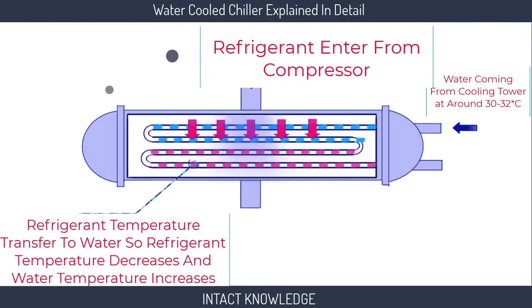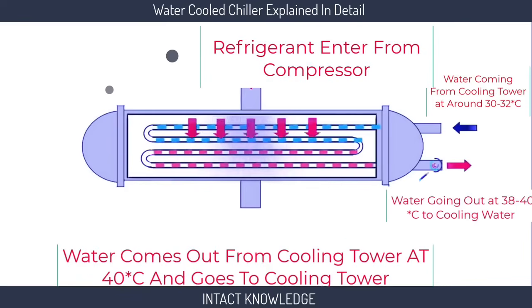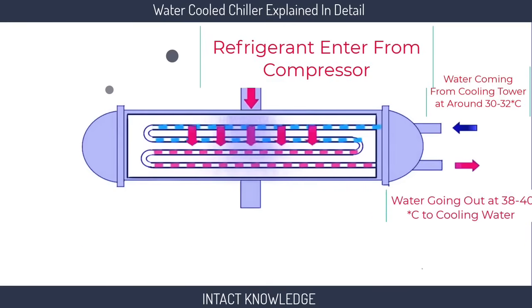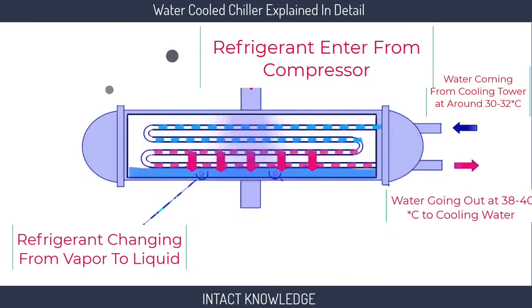Because the refrigerant temperature is higher than the water temperature, the water temperature will increase. The water comes out from the condenser at 40 degrees Celsius. As the temperature of the refrigerant decreases, it changes from vapor phase to liquid phase.